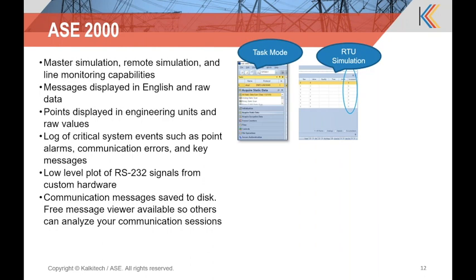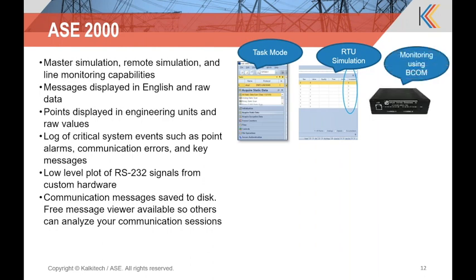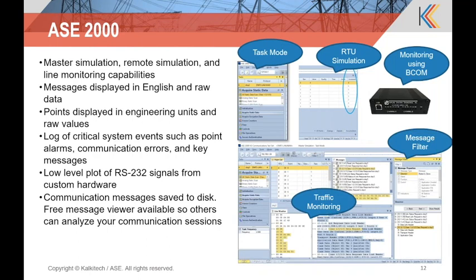And then we also have monitoring using our BCOM, which has the accuracy of up to 100 milliseconds for measuring transmit and receive gaps between the master station and the RTU. So as I said, we can fine tune, or allow you to fine tune, those RS-232 and 485 buses used out in the field. And with our traffic monitoring below, we have a nice window view, which can be user defined. You have some different means of flagging information, both audibly and visually, as it's received.